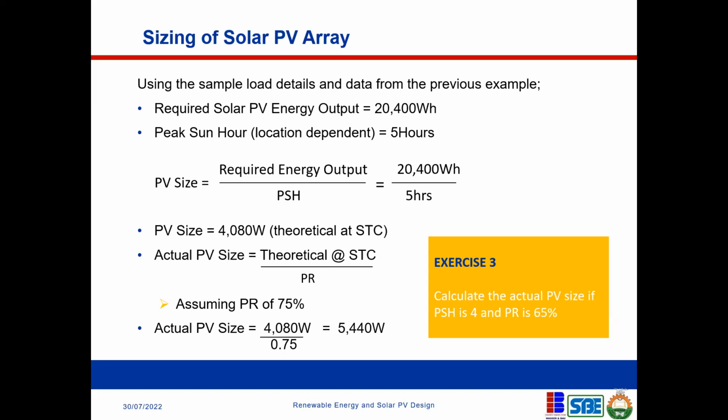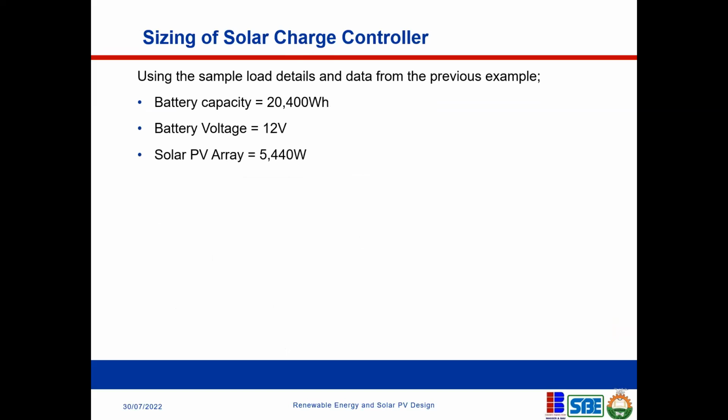Yeah, please. We need 20 rows arrays, because if it's 400 watts rated, 20 modules. Yes, 20 modules too. It is important that everyone tries this calculation, because there could be something that you're getting wrong or you're missing. That's why I included all of this exercise, just to walk us through the process and be sure that we all follow, please. 20 years. Yeah, okay, 20. So let's proceed, please. Everyone, mute your mic.